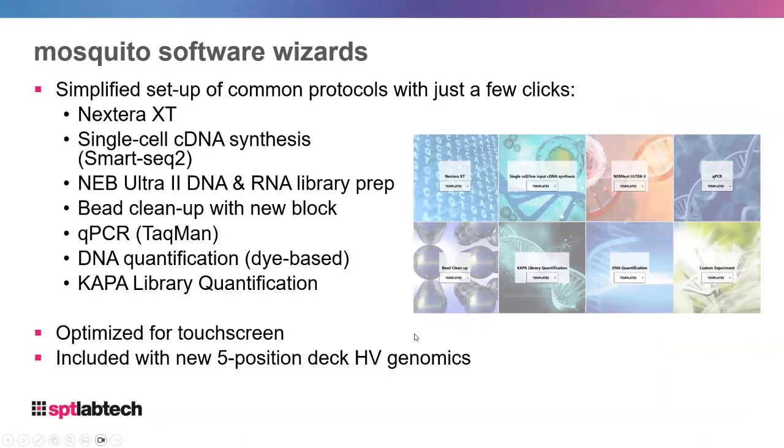The Mosquito HV Genomics comes with a full software package. It contains wizards with simplified setup for common protocols, including bead cleanups, qPCR, DNA quantification, and KAPA library quantification. You also have the ability to set up custom experiments — with the help of your field application scientist you can write a custom experiment for any kit not already listed, to miniaturize the workflows you're actually using.